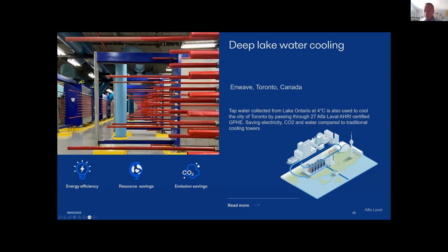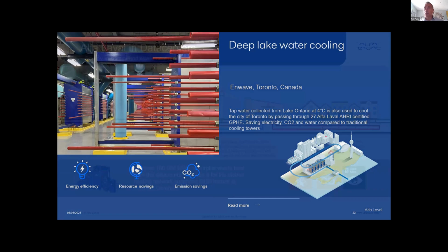Enwave, who run that system, have now also integrated a number of data centers into that cooling network. So they provide cooling to the data centers, and crucially, they're taking the return temperature from their immersion cooling data centers, so they're getting return temperatures of 42 degrees coming back, and they're using that to partly generate hot water in the buildings during the cooling time, the summertime, and then in the wintertime they're using that heat to provide some heating into those buildings as well, or at least at the start of that. And that is a very common application for us, the connection between a data center and a district cooling system.